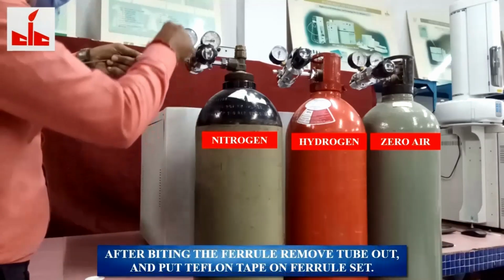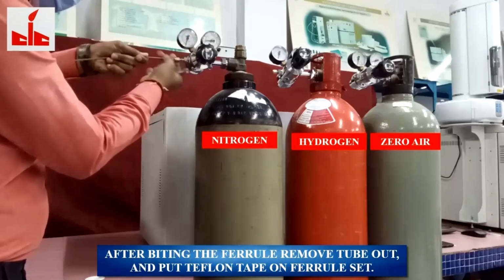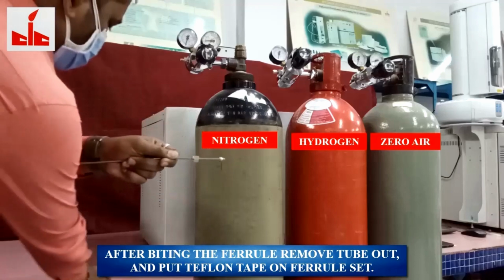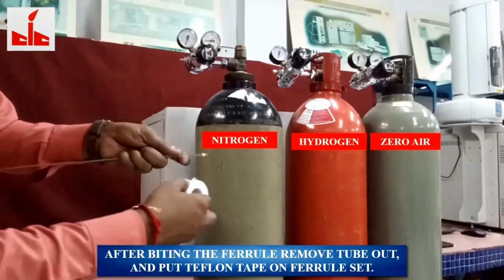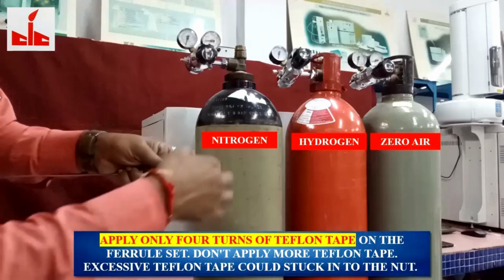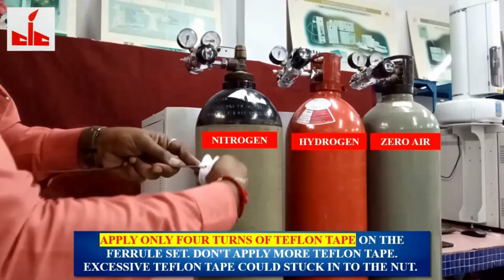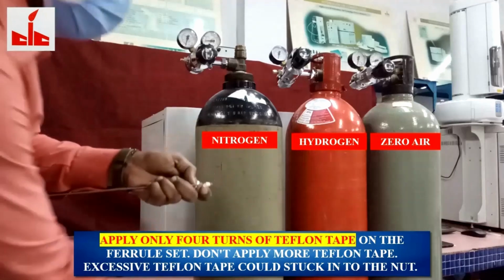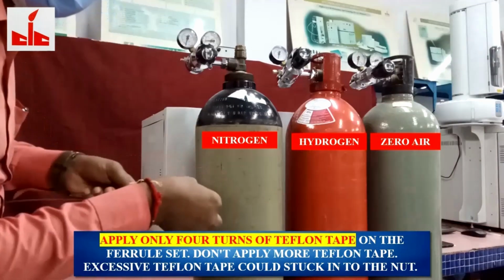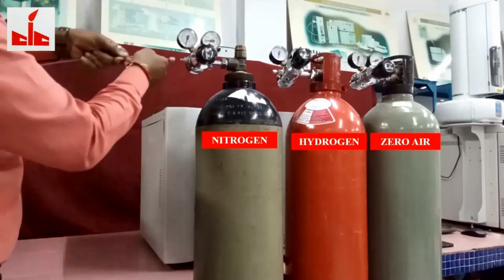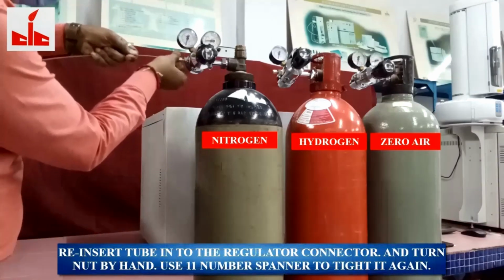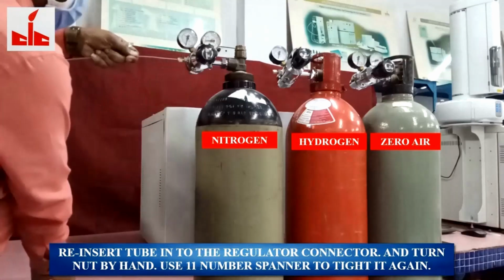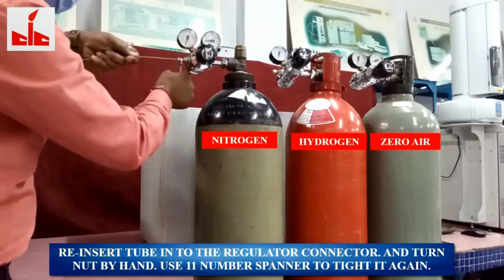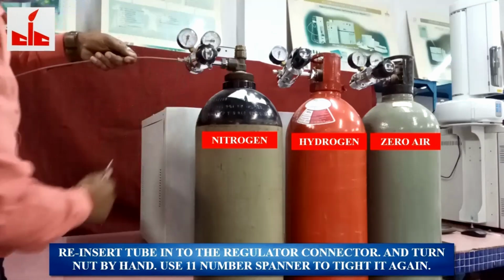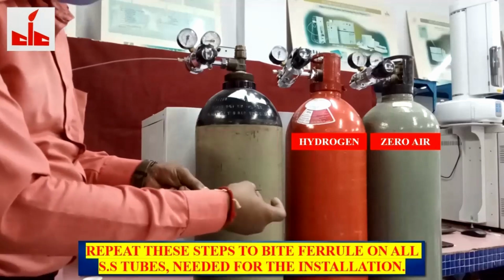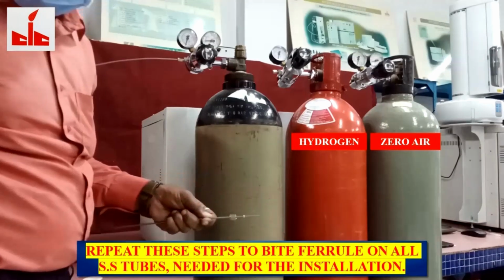After biting the ferrule, remove the tube and put Teflon tape on the ferrule set. Apply only 4 turns of Teflon tape on the ferrule set. Don't apply more Teflon tape. Excessive Teflon tape could get stuck in the nut. Reinsert the tube into the regulator connector and turn the nut by hand. Use the 11 number spanner to tighten it again. Repeat these steps to bite ferrules on the SS tubes needed for the installation.